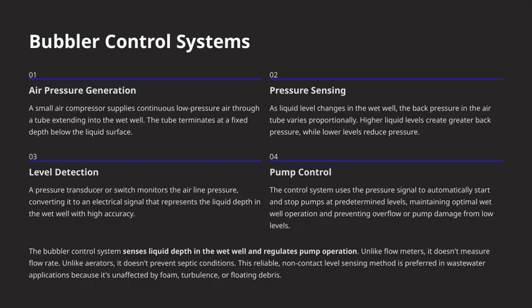It's important to note that unlike flow meters, the bubbler system doesn't measure flow rate, and unlike aerators, it doesn't prevent septic conditions. This makes it a reliable, non-contact method of level sensing, especially in wastewater applications. It's unaffected by foam, turbulence, or floating debris, making it a preferred choice for consistent, accurate level detection.